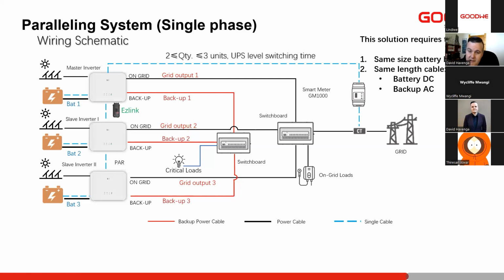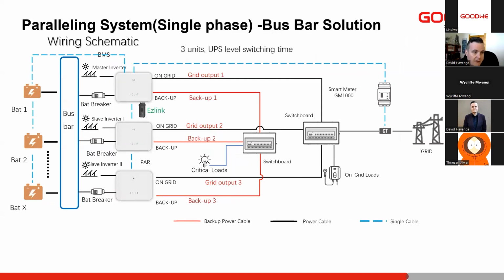So the Ezlink is the only optional accessory you can purchase. With the Ezlink, you'll get 2 cables to connect to have 3 inverters connected. Then you connect your inverters via RS485 to one another. You'll see the smart meter is connected just to here. So there's 2 scenarios. This one is separate battery banks for all our inverters. The alternative scenario is having the bus bar with a large battery bank connected to all of our inverters. So for that, you'll see it will be run through here, connected to the master inverter, the battery communication.